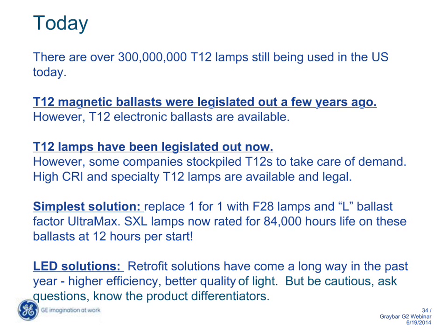I'll tell you one story. We had a customer call us, and they had one of these LED tubes that was meant to be operated on mains voltage to the socket. What was happening is that as they're installing the system, the workers were getting shocked. And so the answer was, well, maybe you ought to ground each tube to the fixture. So these are the types of misses that can happen when you have products that maybe aren't designed as well as they should be. So again, ask questions. Know the product differentiators. What really is going to give you the best guarantee that you're going to have an installation that's not only safe to install, but it's really going to generate customer satisfaction.